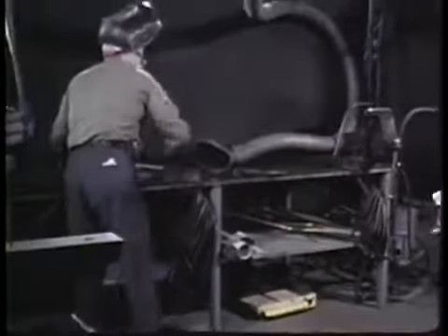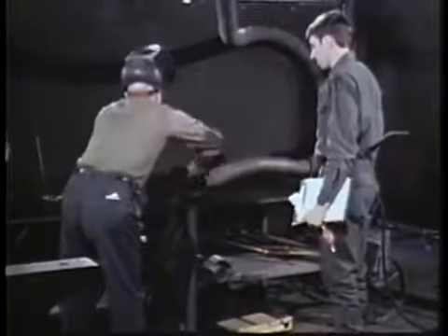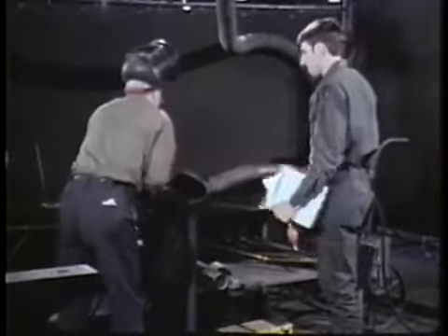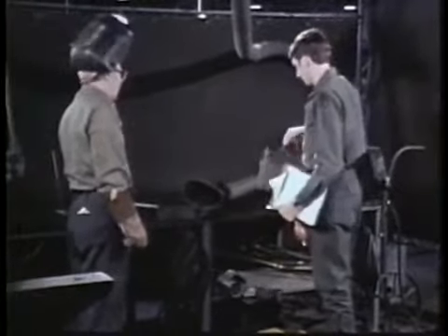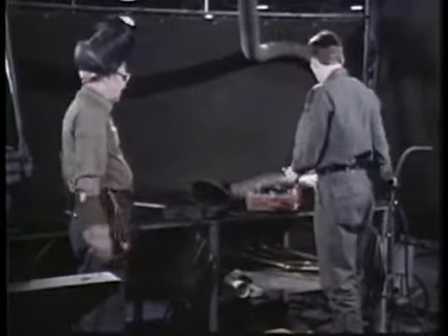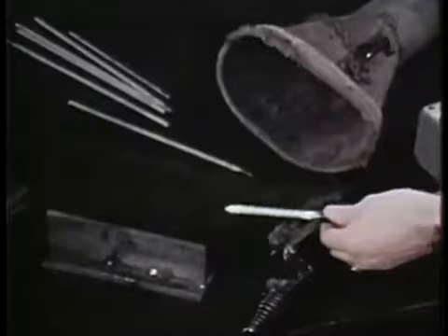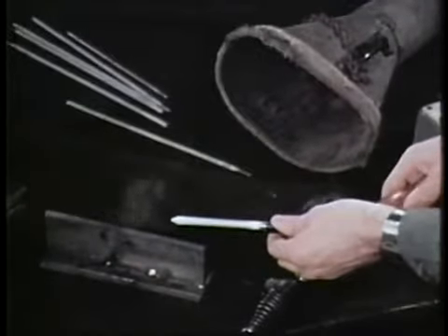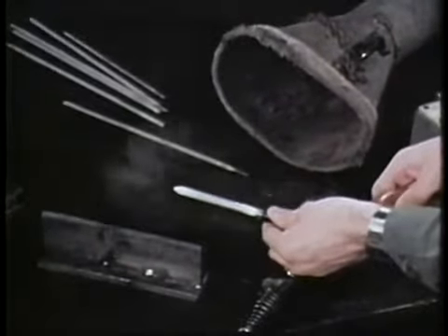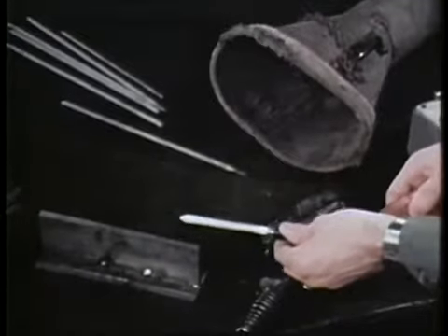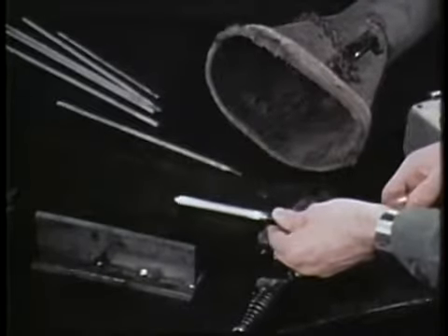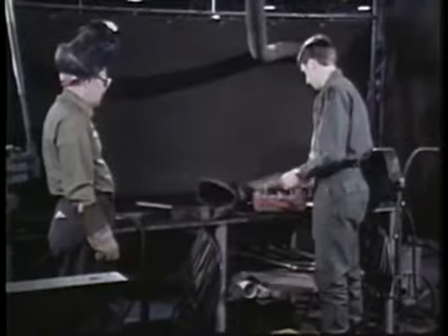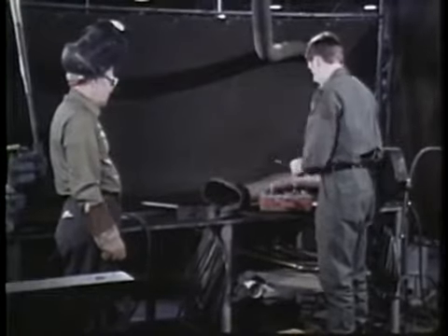Most welders know that welding fumes can be toxic. They know they should use a local exhaust ventilator hood for their own protection. You want to see whether he is using one, whether he's using it correctly, and whether it is moving enough air to be effective. You'll be able to visually check how the ventilation hood is performing with the aid of a ventilation smoke tube. The actual air velocity you measure with the anemometer in the usual manner.